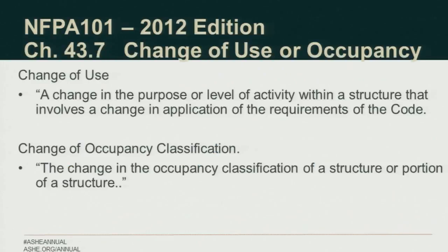Next, we're going to go to change of use and change of occupancy. So anyone care to define the difference between the two? A change of use is something that stays within the same occupancy. I'll use a great example for healthcare. If I've got a patient room that I want to now use for storage, that's a change of use. It's not a change of occupancy. It's still an I2 occupancy, but it's a change of use.